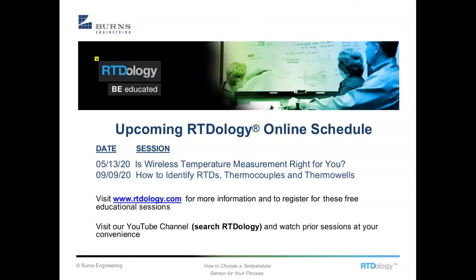Okay. And another question: is there any merit to using a less thermally conductive head, for example a plastic versus metal head, when looking at the accuracy and stem conduction error? Yes, it does make a little bit of a difference. I think the majority of the conduction error that we see happens on the lead wires, but the rest of it does make a difference. Things that are less thermally conductive certainly help minimize stem conduction. We've even used PVC or other plastic extensions rather than galvanized steel or stainless. Stainless actually is not a very good conductor of heat, but plastic is even less of a conductor, so it would certainly make a difference.